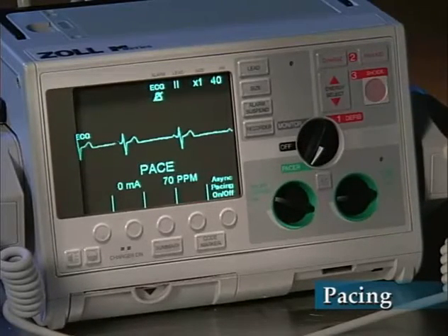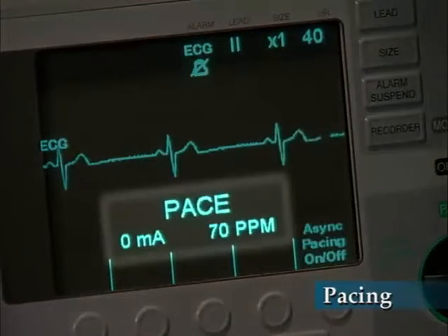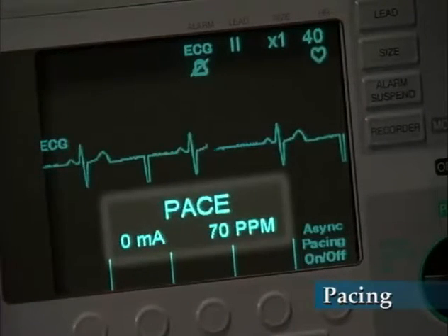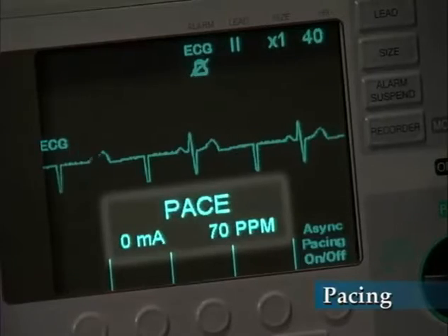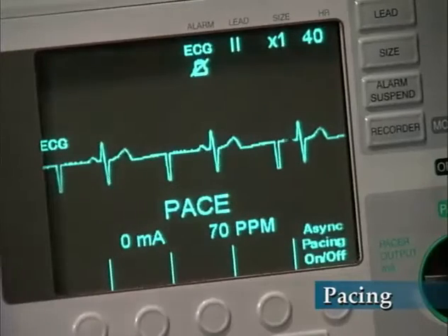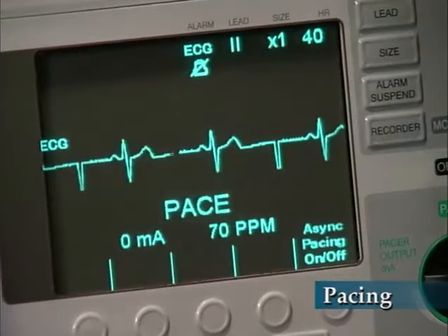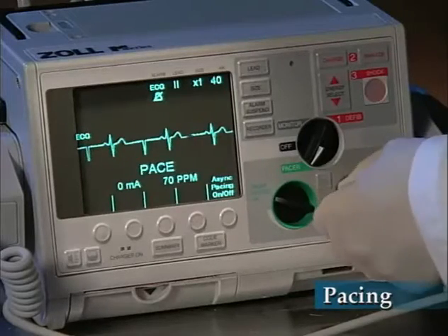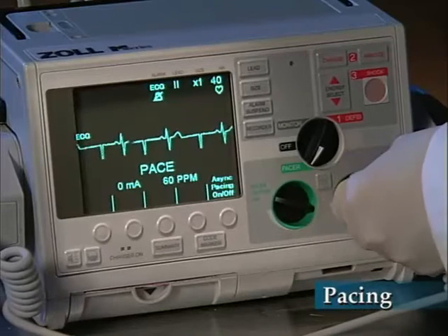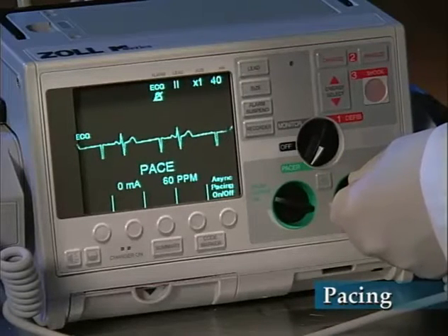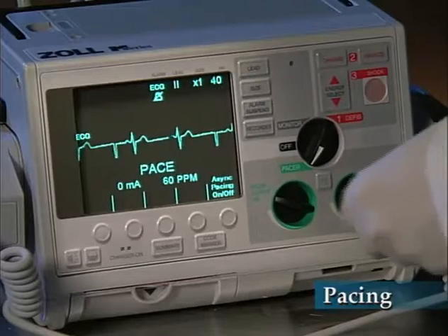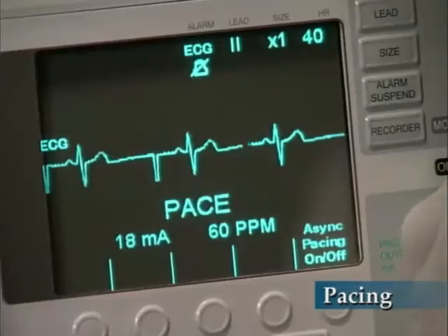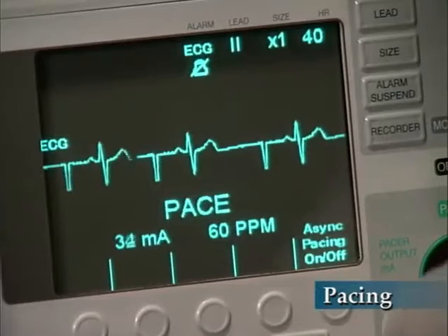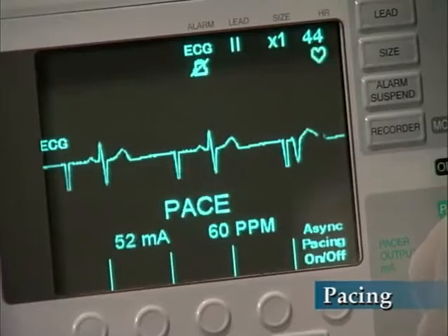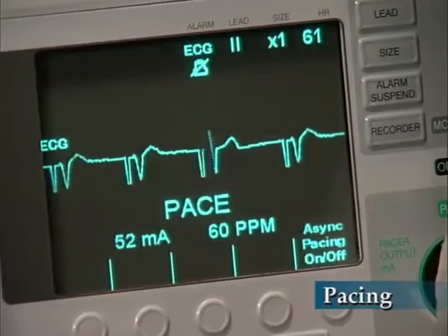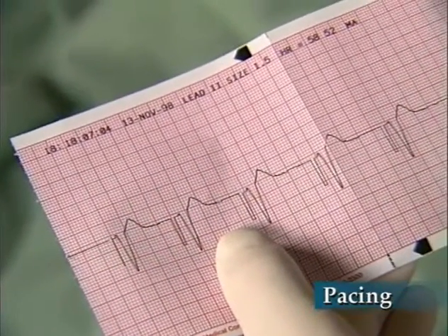The Pacer output will automatically be set to 0 milliamps, mA, and the Pacer rate at 70 pace pulses per minute, ppm. Prior settings will be retained if previously set and the unit was turned off for 10 seconds or less. Set Pacer rate to a value 10 to 20 ppm higher than the patient's intrinsic rate. If no intrinsic rate exists, use 100 ppm. Increase the Pacer output until stimulation is effective. Observe the pacing stimulus marker on the display or strip chart to verify that it is well positioned in diastole.